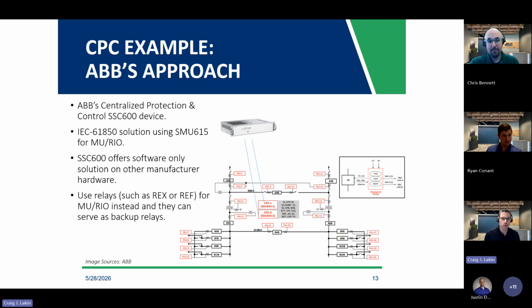So in this example, in theory, you could have your two CPC devices, and then all these merging units could also be acting as backup relays, which means if the CPC itself goes down, you're not completely out of water on your protection. You still have your backup elements in more of a traditional approach. So that's another good way to kind of implement a system 1 and system 2 protection scheme. You could go with a merging unit and then a backup relay, or you could go with a merging unit and then another merging unit and two relays. It kind of depends on what your cost versus benefit is on your analysis on how you want to implement CPC.